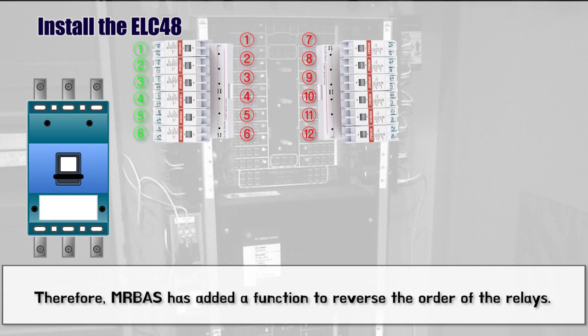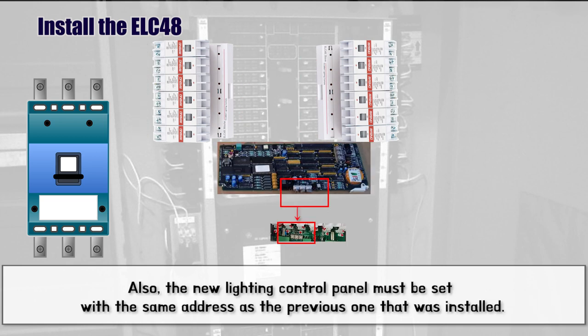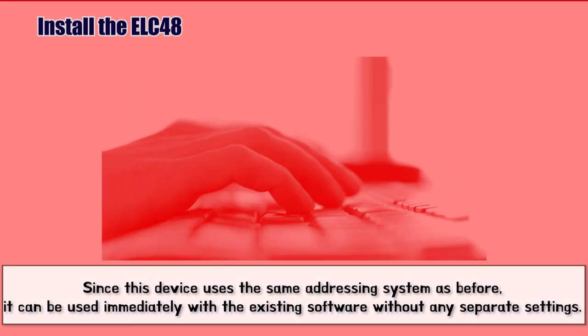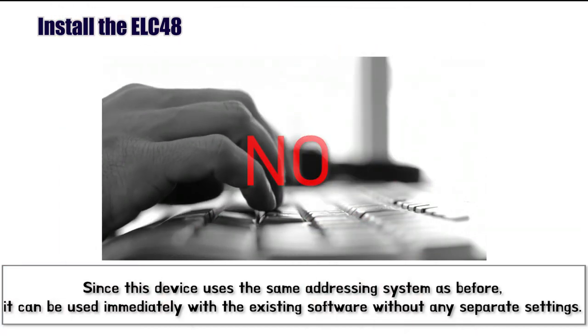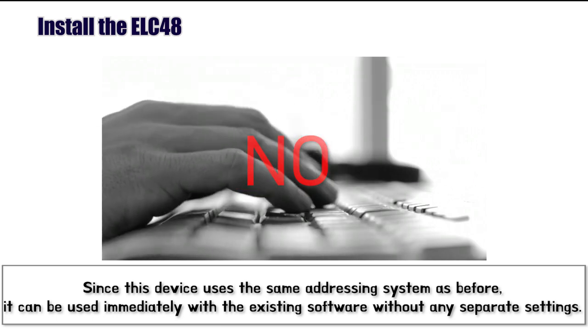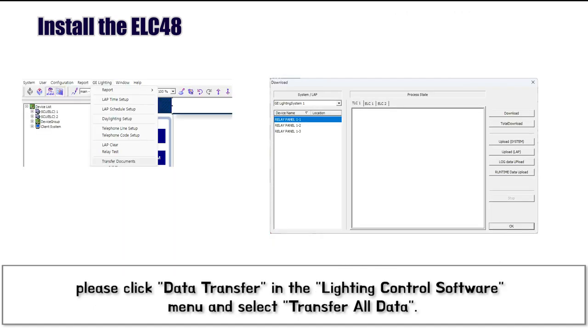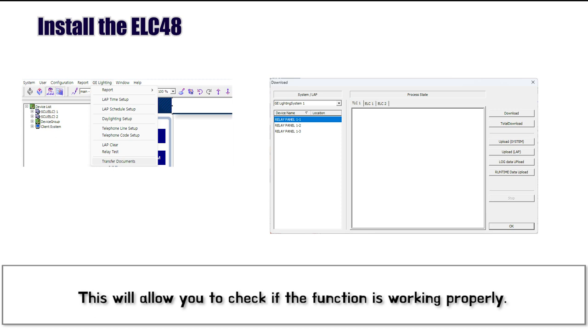Therefore, MRBAS has added a function to reverse the order of the relays. Also, the new Lighting Control Panel must be set with the same address as the previous one that was installed. Once all connections are complete, turn on the Lighting Control Panel circuit breaker and lamp circuit breaker that were turned off at the distribution board. Since this device uses the same addressing system as before, it can be used immediately with the existing software without any separate settings. If you are using other functions such as schedules or PSS, click Lighting Control Software Data Transfer and then Full Data Transfer to confirm that the functions are operating normally.